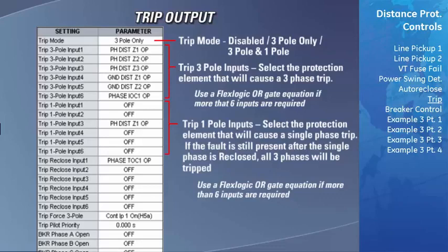The next 6 fields that are labeled Trip 1-pole Inputs 1 to 6 are only used if the trip mode setting was set to 3-pole and 1-pole. If they are being used, you need to enter all of the protection element output operands that you want to trip only the faulted phase when a fault is detected.